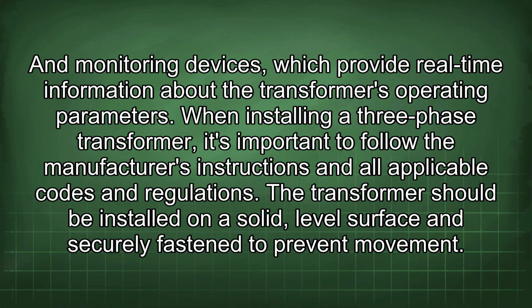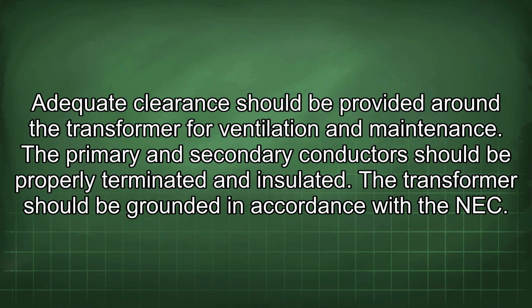When installing a three-phase transformer, it's important to follow the manufacturer's instructions and all applicable codes and regulations. The transformer should be installed on a solid, level surface and securely fastened to prevent movement. Adequate clearance should be provided around the transformer for ventilation and maintenance. The primary and secondary conductors should be properly terminated and insulated. The transformer should be grounded in accordance with the NEC.